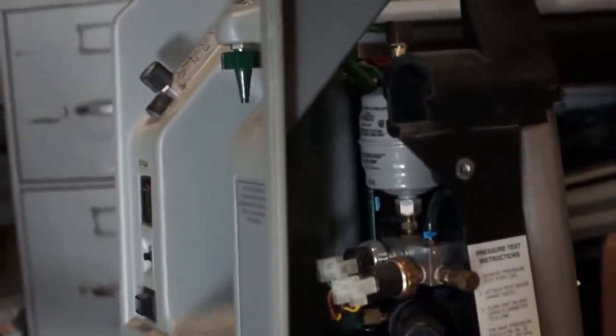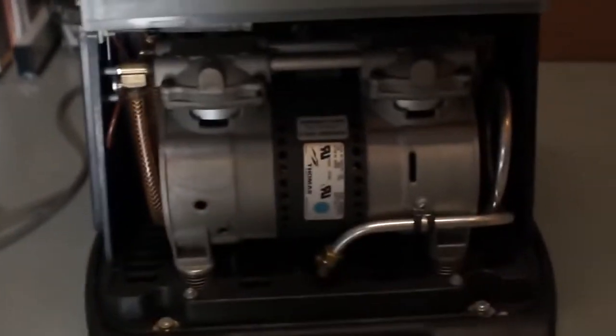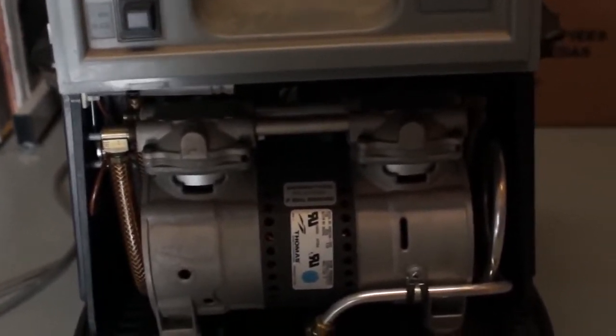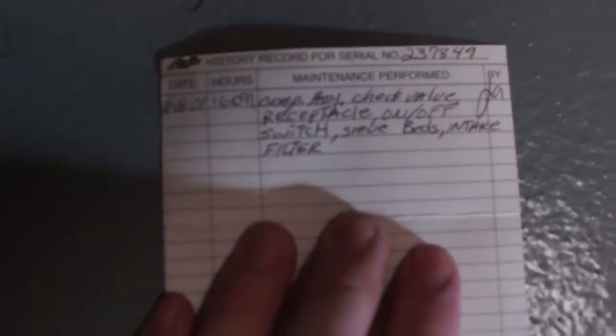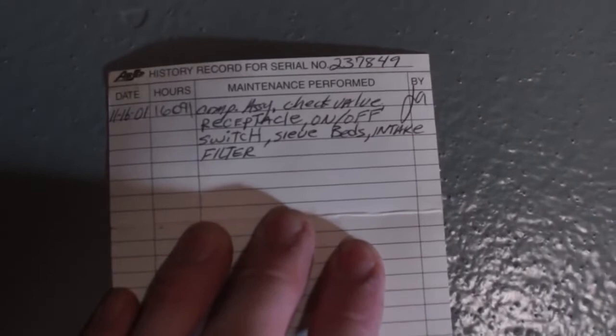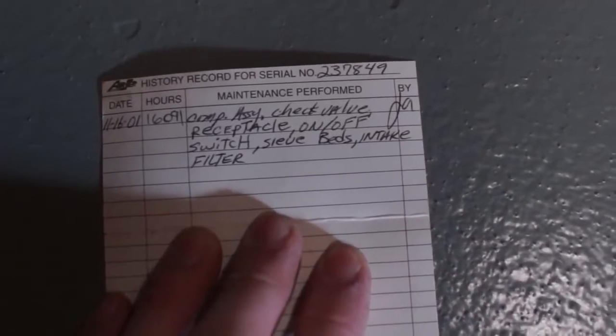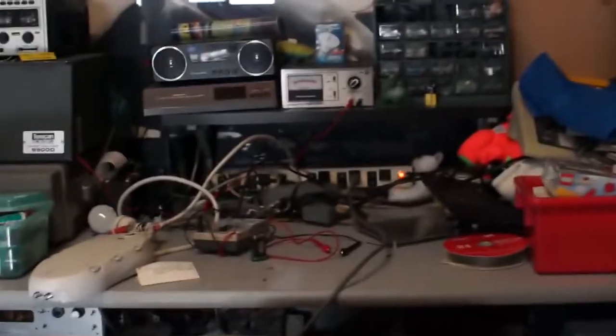I'm gonna look closely at that circuit board for any failed components. But I'm imagining if it's just throwing the circuit breaker, something major failed. Like this motor, I can disconnect the compressor and just plug it back in and see if everything else turns on. That would tell me right away if it was a dead short in the coil or something like that. Here's a little maintenance card that I found in here. It was last worked on in 2001, and at the time it had 16,000 hours. Okay, I'm going to do a straight power test. He said that it was blowing circuit breakers.